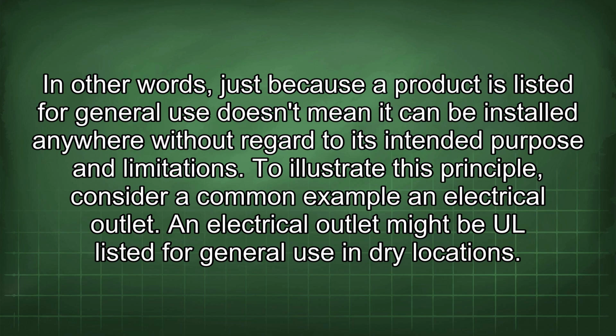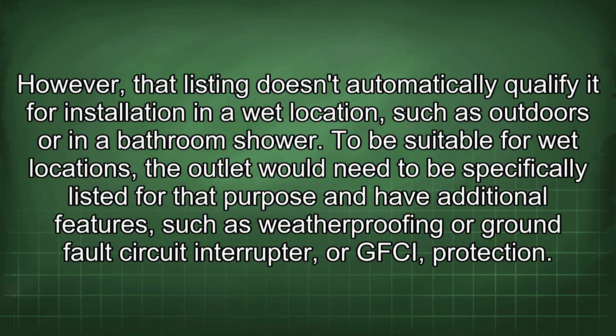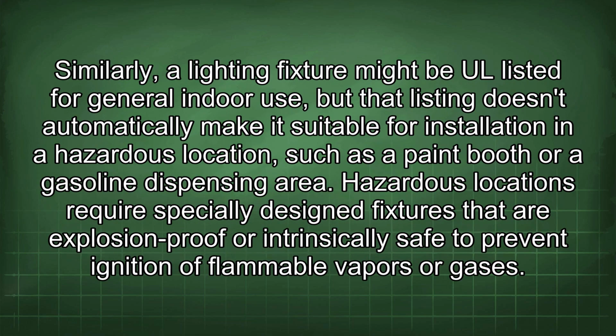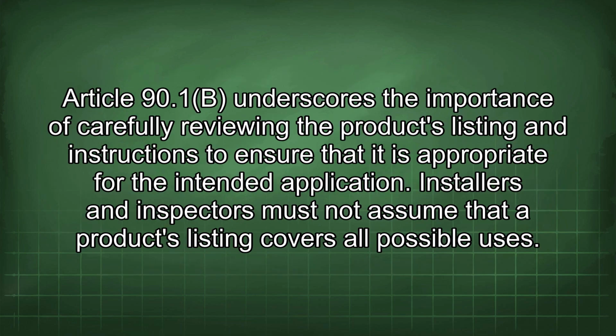To illustrate this principle, consider a common example: an electrical outlet. An electrical outlet might be UL listed for general use in dry locations. However, that listing doesn't automatically qualify it for installation in a wet location, such as outdoors or in a bathroom shower. To be suitable for wet locations, the outlet would need to be specifically listed for that purpose and have additional features, such as weatherproofing or ground fault circuit interrupter, or GFCI protection. Similarly, a lighting fixture might be UL listed for general indoor use, but that listing doesn't automatically make it suitable for installation in a hazardous location, such as a paint booth or a gasoline dispensing area. Hazardous locations require specially designed fixtures that are explosion-proof or intrinsically safe to prevent ignition of flammable vapors or gases. Article 90.1b underscores the importance of carefully reviewing the product's listing and instructions to ensure that it is appropriate for the intended application.